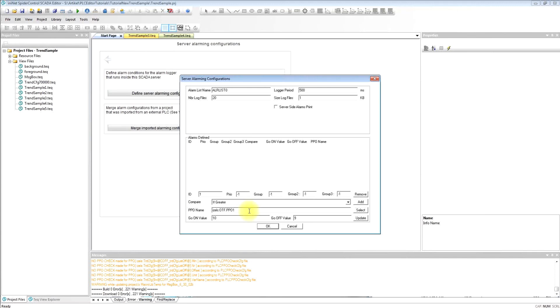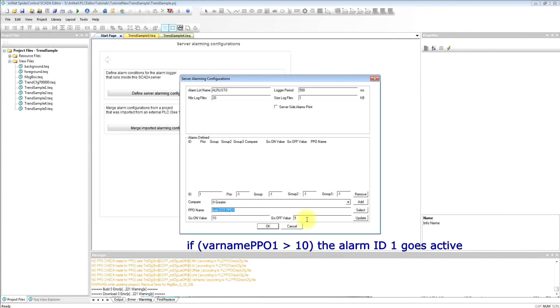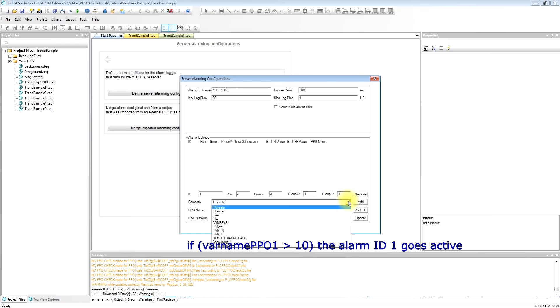We will use three test variables, three PPOs, and define conditions when the alarms will be fired. So if this PPO1 is bigger than 10, the alarm will become active, and if it falls below 9 it will be inactive.